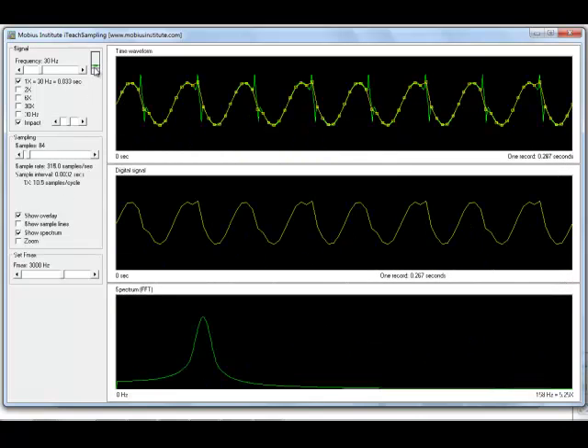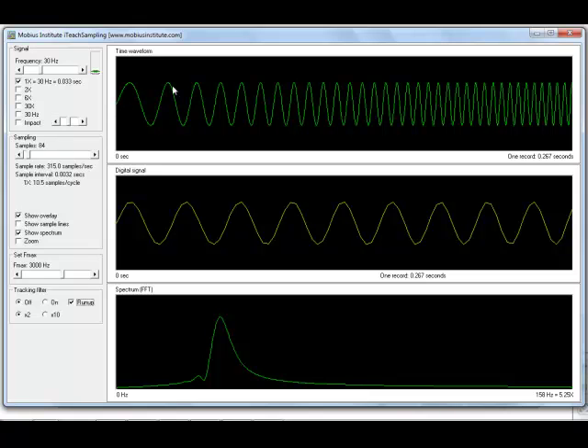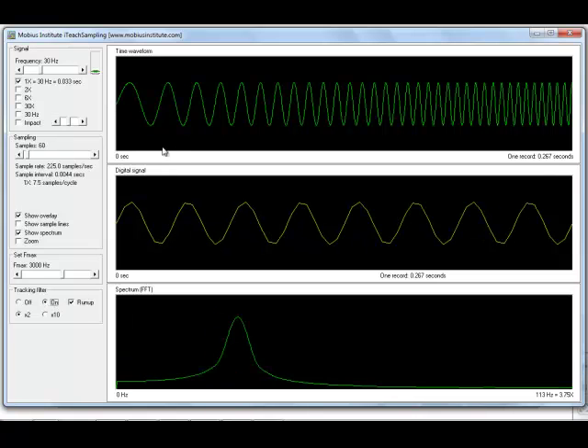There's much more this simulator can do. We can get into the spectrum analysis part of it, and even look at what happens if the machine is changing in speed. In this case we've got a machine going faster and faster. If we use normal sampling techniques — meaning a fixed time between samples — our spectrum will be hopeless: all broadened and the amplitude will be down. So instead we use a tracking filter, making the sample rate in proportion to the speed of the machine. We watch the speed and adjust our sample rate accordingly, ending up with much better data.